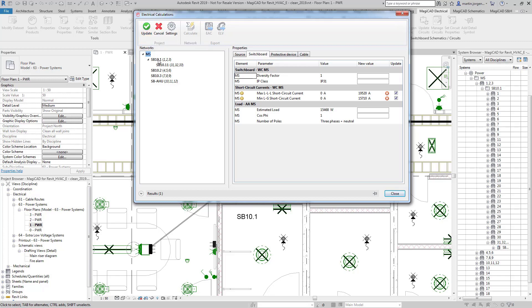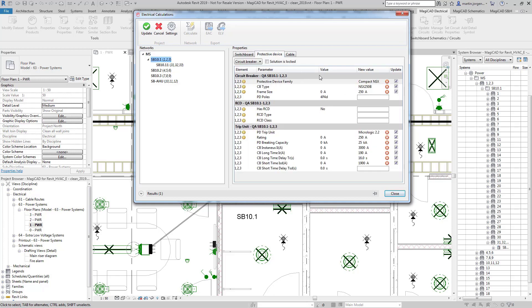So here in SB10.1 I can see again I've got my maximum and minimum short circuit currents calculated here but also I have the protective device selected. So the calculation engine has gone through the network and run various checks to check discrimination and to check short circuit current, volt drop, etc. and calculated that this particular circuit breaker selected from the Schneider product range will work with my installation.